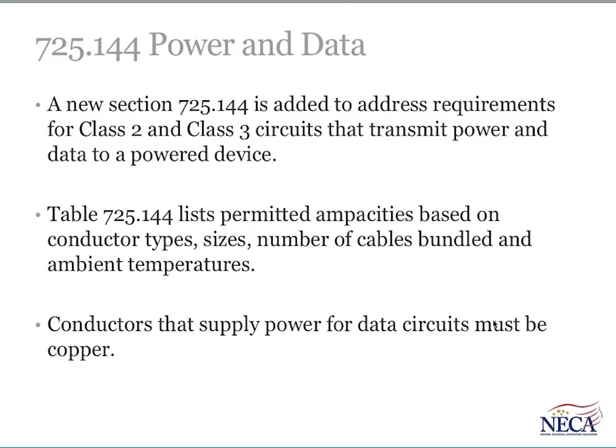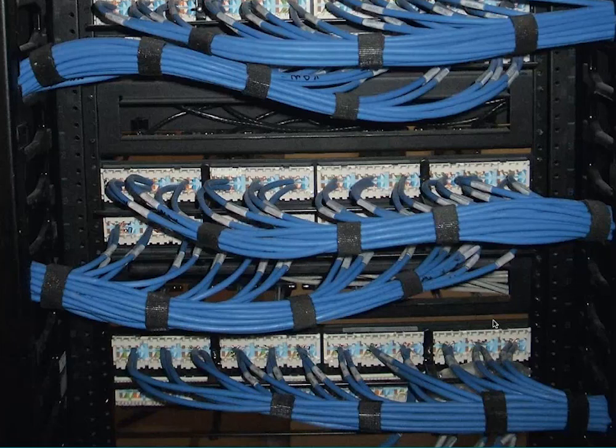725.144 is new, and it was added to address Class 2 and Class 3 circuits that transport power and data to a powered device. In other words, we have to make sure that we're controlling the amount of power that's being used over these types of cables. And there's a new table, 725.144, that lists the allowable ampacities based on the conductor sizes and types and number of cables bundled within the installation. For example, if you're using this type of cable and you start transporting power within this type of cable, you can see, especially with this photo, where you could get into a problem depending on the amount of power being used in addition to data within the same cable. You start bundling and you start having problems with heat.